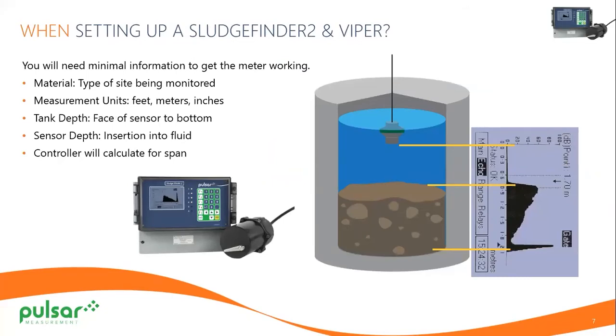So, super intuitive. When setting up a Sludge Finder 2, you need minimal information. Material type of site being monitored. Is it industrial, primary, or secondary clarifier, an SBR? Measurement units, whatever you want to read in, feet, meters, inches, tank depth, face of the sensor to the bottom of the tank. So if you look over on the right, we have the sensor in the drink, which is the top yellow line. Then we have the sludge settlement level, which is the middle line. And then we have the bottom of the tank.